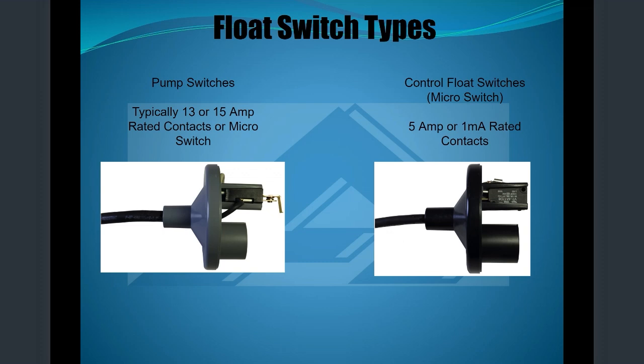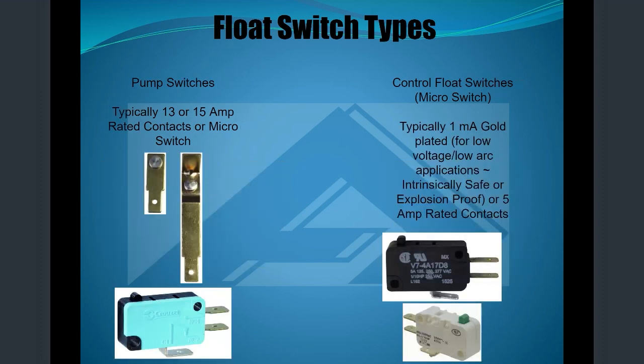And then on the right, we use a micro switch up in here, and we have a 5 amp or 1 milliamp rated contact. And so those cannot take the full load amps of the pump. So if you connect those to your pump, you're going to get a short circuit. And here's a little different look at the metal contacts on the left. And on the bottom left, there is actually the new micro switch that we're using.